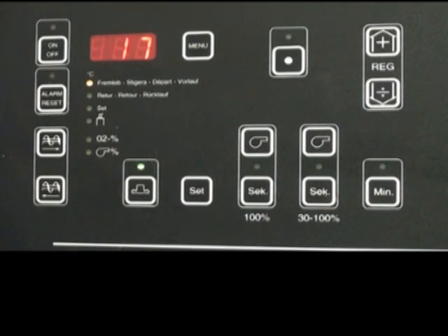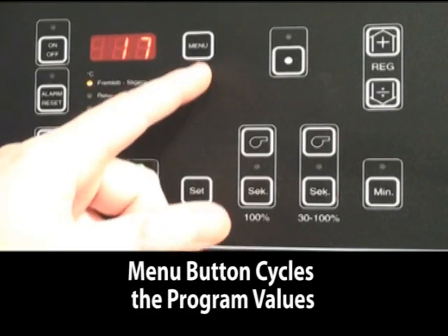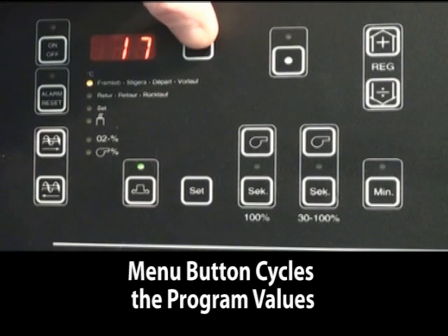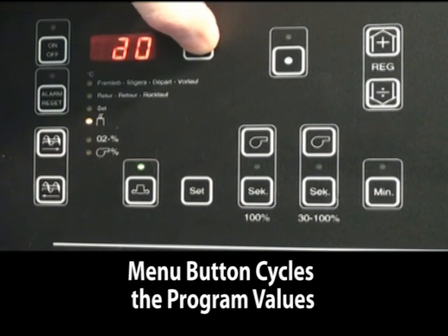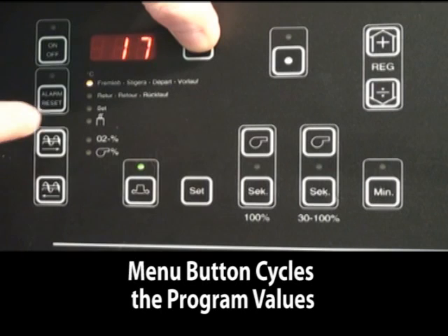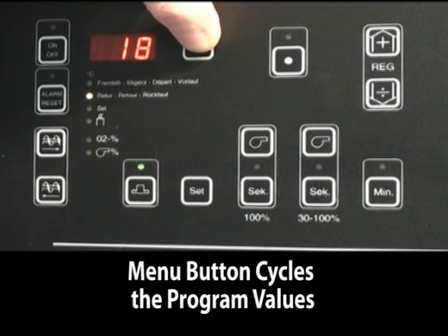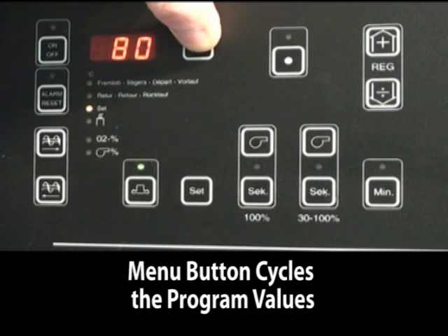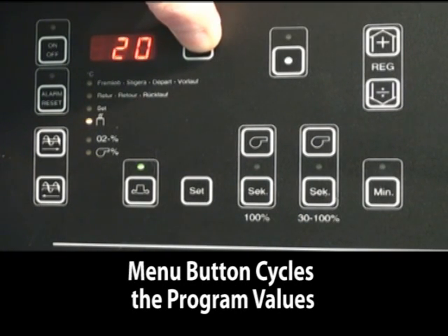Some other functions on the control panel. If you hit the menu button, it cycles through all these readings. The first reading is the supply temperature. The second one down is the return temperature. The third one down is the set point of the boiler. And lastly, that is shown as the flue temperature.